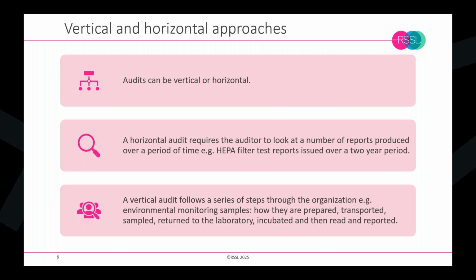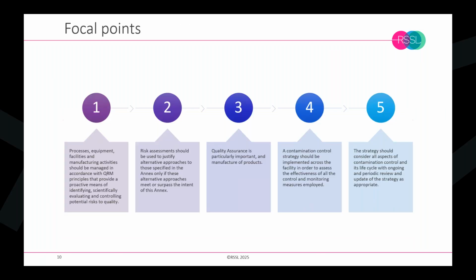So the example on the slide might be, if we're going to look at HEPA filter testing, we're not just looking at what was done last time. We'll be looking at the overall trend. Are we having certain issues of failure? Is our pressure hold across our filter decreasing, which might raise contamination concerns? But here we're talking today about contamination control audits specifically.